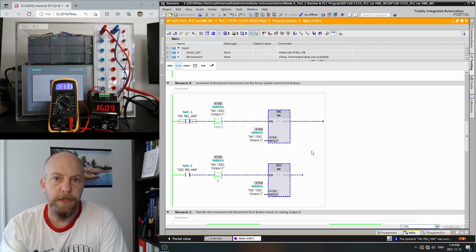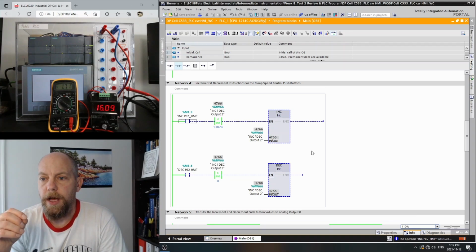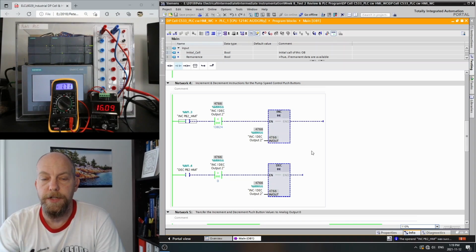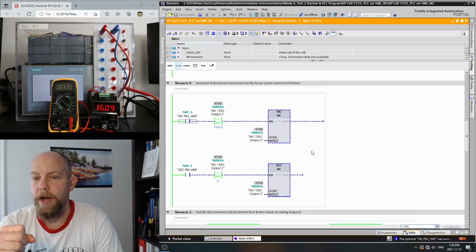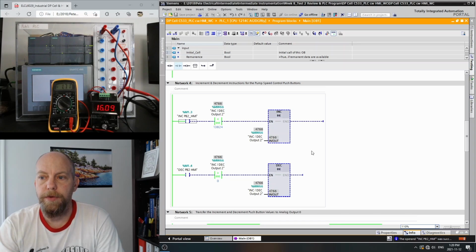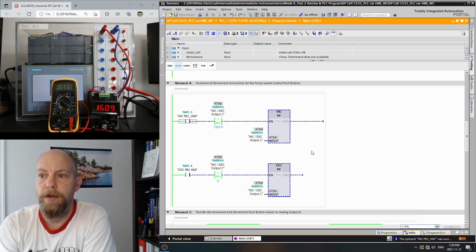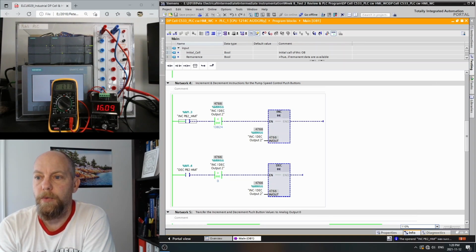A couple of things that you may have noticed. For one, we've got a negative value here. Some of the analog outputs were miswired in that your positive is actually your negative and negative is the positive for some reason. I think that after 40 different boxes, they were backwards. And you'll see that I'm on analog output number 2. So double check, because we're supposed to be on analog output number 1, but I think those two were miswired on my box here, so I'll have to rewire those. Regardless, we have 1.71 volts coming out.